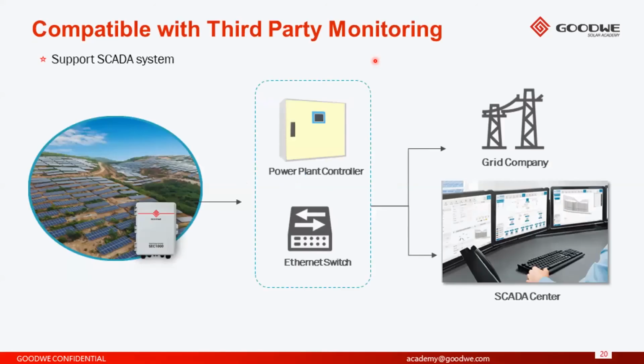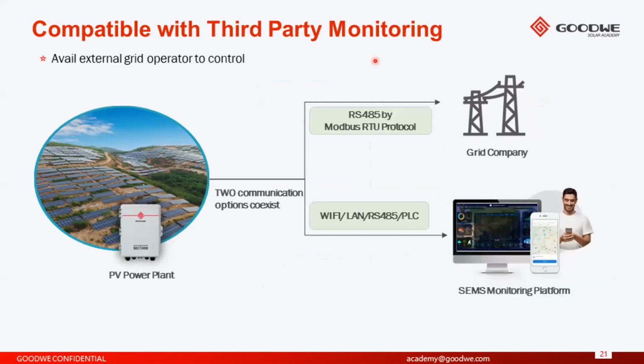So as I mentioned, our SCB or SEC 1000s have the capability to connect to a power plant controller, which is sometimes necessary. Sometimes the grid connection stipulates that the PV plant must have a power plant controller, which allows the grid company to control the output or certain settings of the PV plant itself, and also allows the grid company to communicate and extract data from the PV plant. And this can also be done by RS485 using the Modbus RTU protocol.